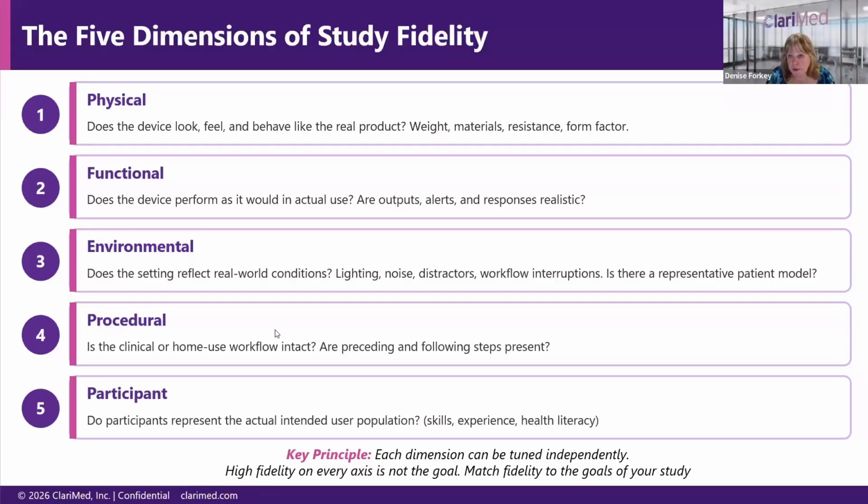So as you're looking through and designing your formative evaluations, really it's key to think about what is your overall goal, and then what are the parts of that study fidelity that are most important for you to meet your goal without producing data that may lead you in a direction that's incorrect. So as you're thinking through that, you don't have to design all of these perfectly in your formative studies. You can look at each one independently and maybe dial in higher fidelity for one of the features that you find will most impact the overall success of your study.